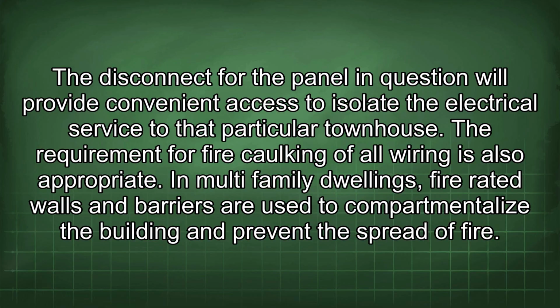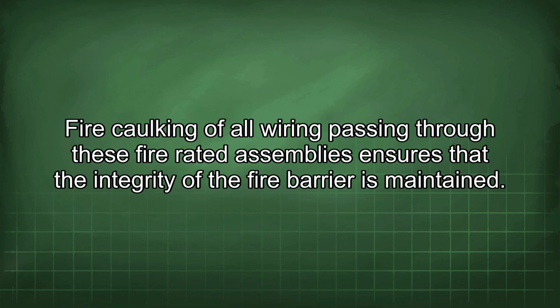The requirement for fire caulking of all wiring is also appropriate. In multi-family dwellings, fire-rated walls and barriers are used to compartmentalize the building and prevent the spread of fire. Fire caulking of all wiring passing through these fire-rated assemblies ensures that the integrity of the fire barrier is maintained.